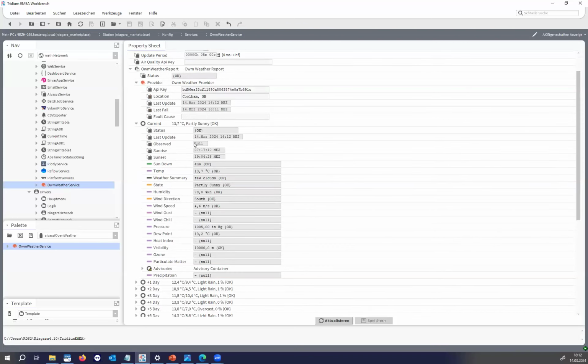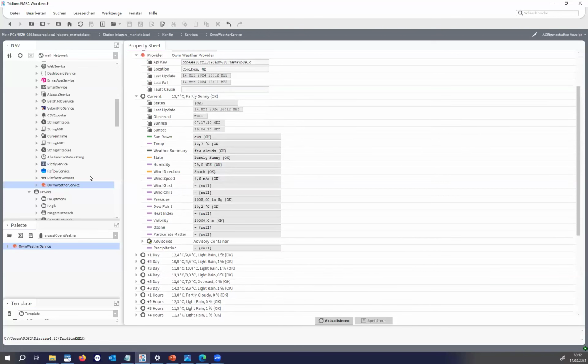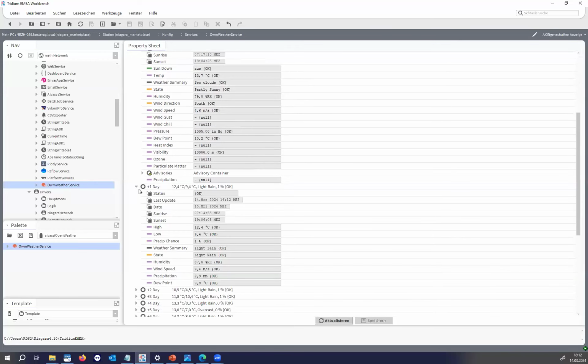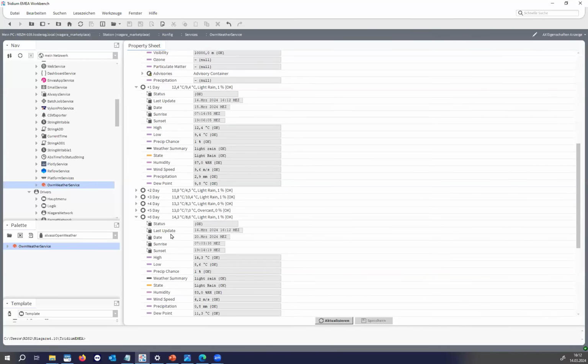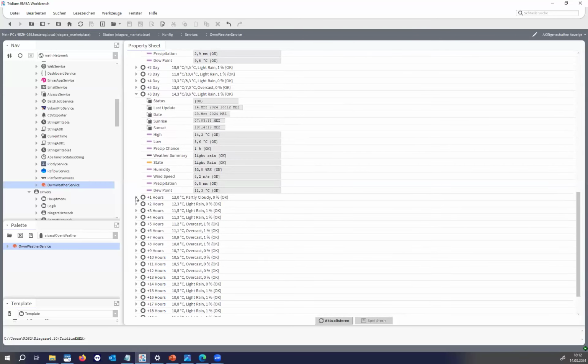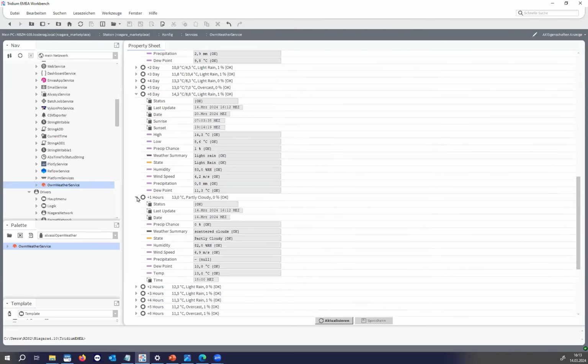The current value has different values inside: temperature, state, humidity, chill, and so on. You can use this because it's a data point in the Niagara framework, and use it in your logic. You have the forecast - current day, 1 day forecast, 2 day, up to 6 day. And for coolness, you have the 1 hour prediction temperature at 6 o'clock - here you have the value, and you can use it.